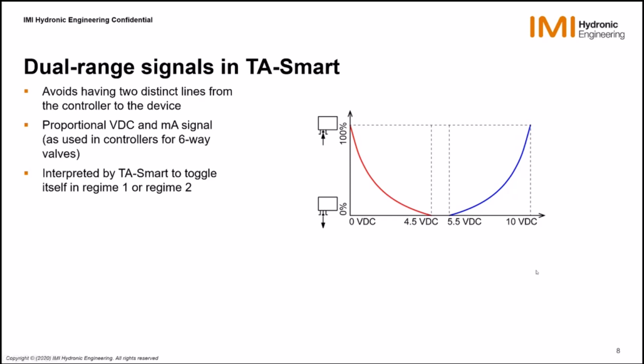The first area is the regime 1 area in red, where we are going to do proportional control according to the chosen characteristics. If we are in flow control with TA-Smart, we will get an equal percentage characteristic like this. At 4.5 volt, the valve is shut, and at 0 volt, the valve should reach the max flow that is set for regime 1. Of course, here, the valve will not necessarily give you 0 flow or be shut, because you might have defined a minimum flow that is not 0. So here we are simply applying the opening and closing of the actuator according to the corresponding control mode.